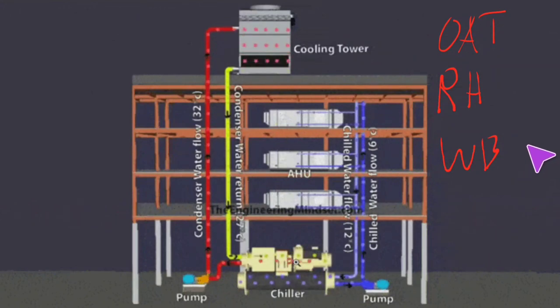As you're calibrating your plant, usually I will have my automation system set up to where the condenser water temperature will be whatever the wet bulb temperature is plus five degrees is the condenser water set point. In addition to that, there'll be an extra parameter where it will not allow the set point to go below 60 degrees if it's a York and 80 degrees on that modulated set point, meaning it'll limit at those two temperatures. If it was a Trane, again, I would do something like 70 degrees and 85 degrees. That way no matter what happens, I know that I'm somewhere between the ranges I want to be and I can make that system run as efficiently as possible.